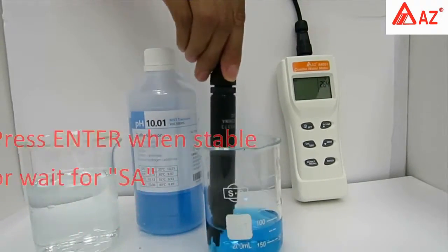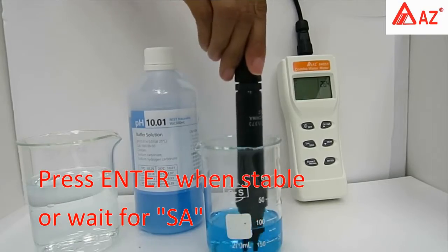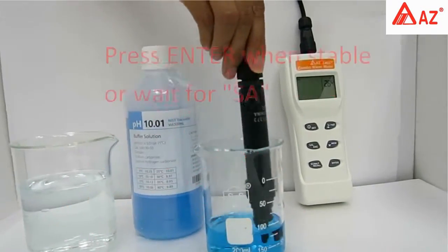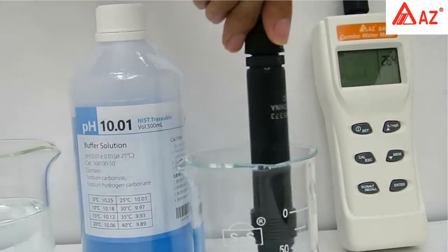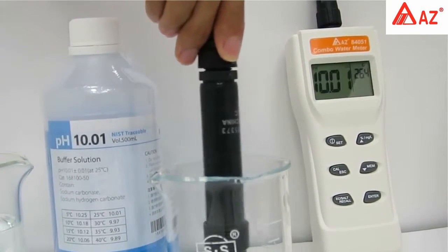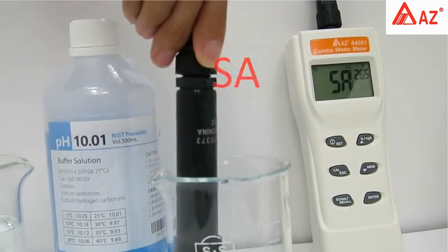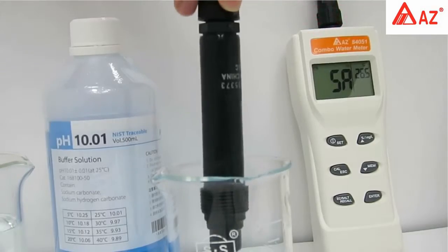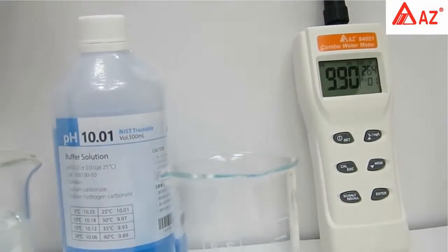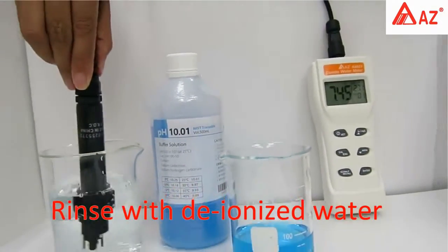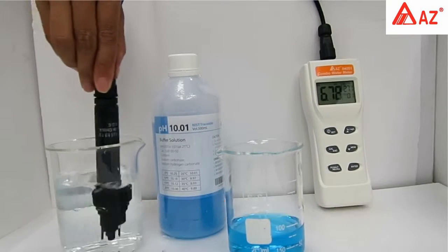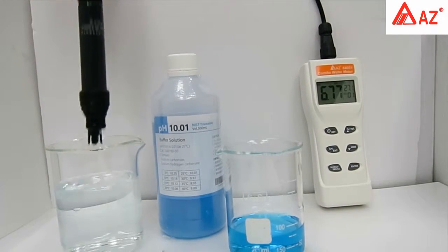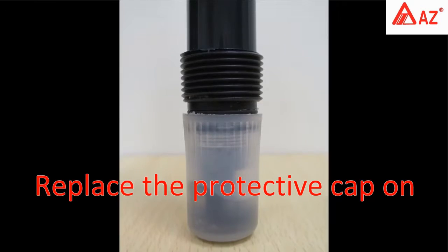Once the reading is stabilized, press enter, or wait for the SA icon to appear when the result is automatically saved. Rinse the probe with deionized water after use. Dry the glass bulb and replace the storage cap.